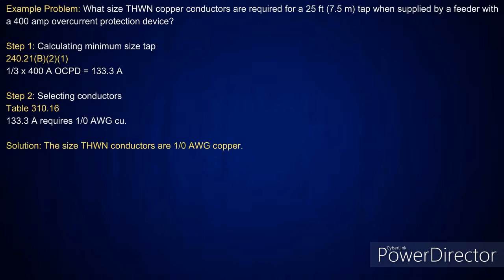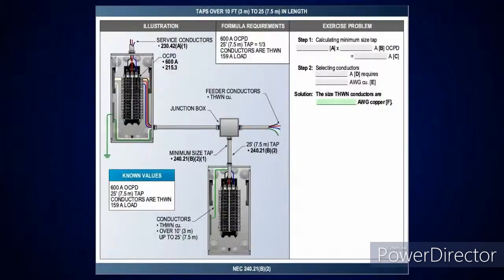So simple. So with that calculation, you're saying that is anything from 11 foot to infinity? Anything, it doesn't matter how long it is. I can go up to 100 foot and you're still going to take it at a third. There are just other rules that you follow, and I'm going to prove that. But if it's outdoor, you don't have to do any of this, right? It's different. And I'm going to get into where it's not a tap and we're doing secondary conductors.